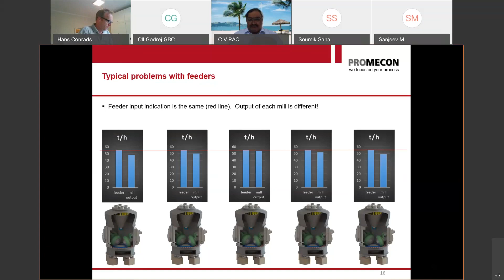So what do we do to prevent that? Promecon has a system that can measure the coal mass flow out of the mill in real time, telling you how many tons per hour or kilograms per second are coming out of your mill right now. This has a huge impact: you can level out your mill output, get a better distribution of coal in the boiler by reducing imbalances, and the real-time output also lets you increase load flexibility on your boiler. I'll show you an example of that at the end.